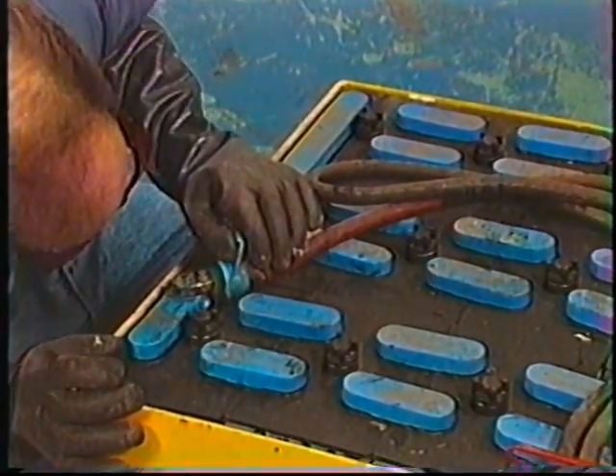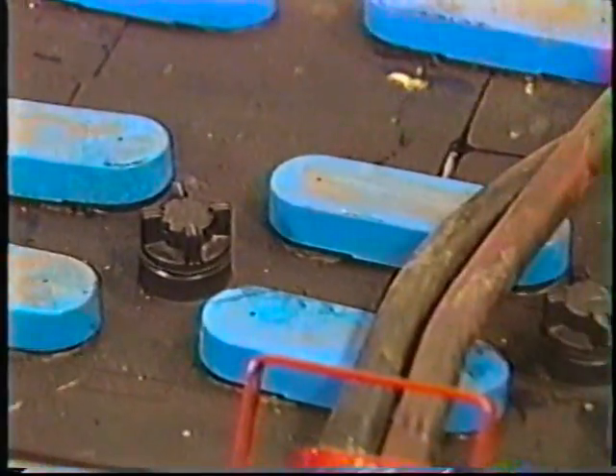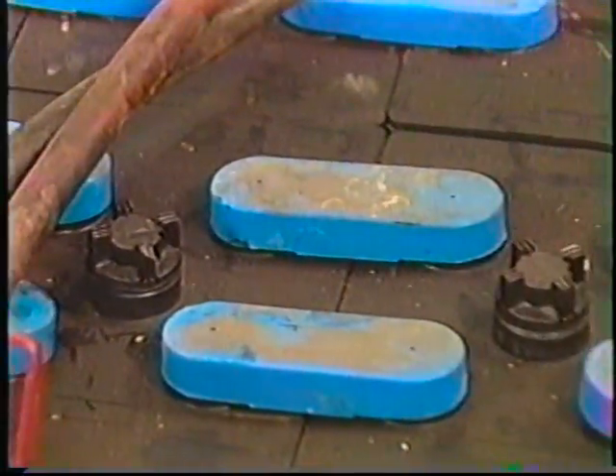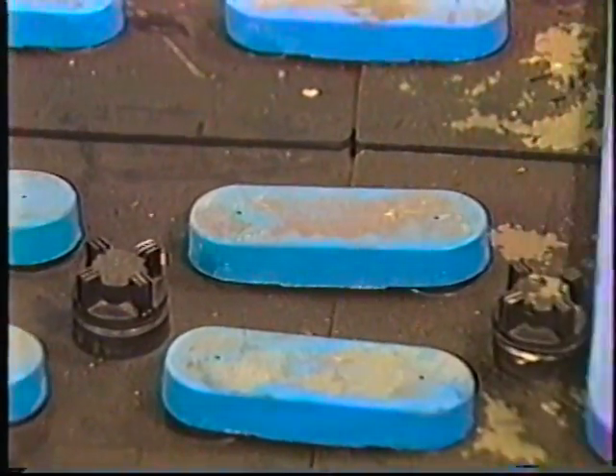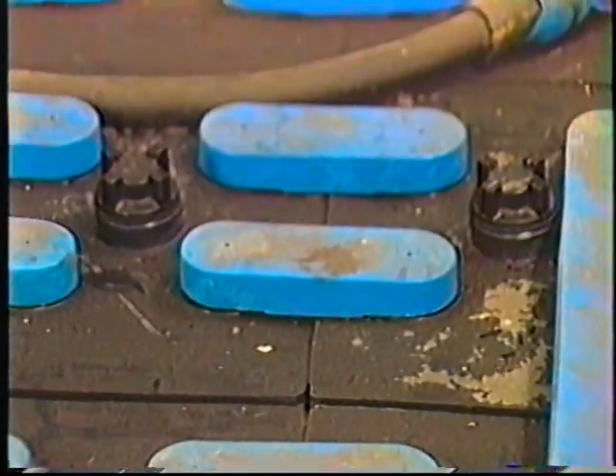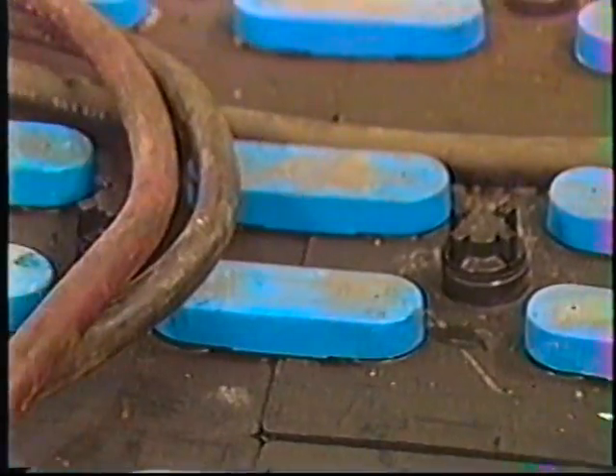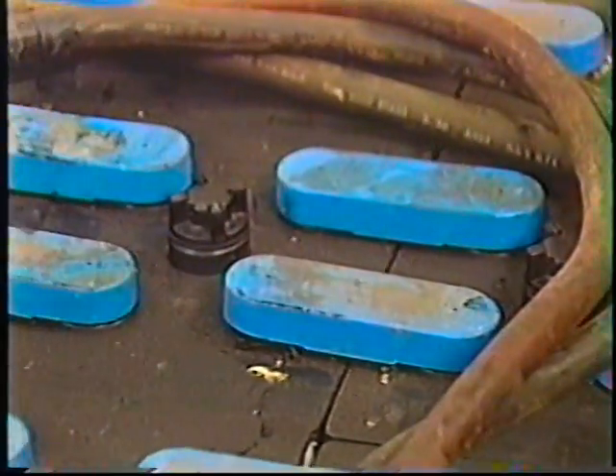Next, look for any signs of corrosion, dirt accumulation, or wet areas caused by electrolyte spilling across the top or sides of the battery. This contributes to battery current leakage, which we'll cover in more detail later.